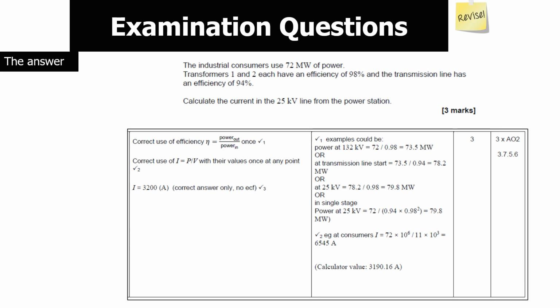The first point is at 132 kilovolts with an efficiency of 98%, so we do 72 over 0.98, giving 73.5 megawatts at that point. The next section has an efficiency of 94%, so we divide by 0.94, giving 78.2 megawatts at the start of transmission. Then you work it all through, pop in your values, and at the end do I equals P over V to get the answer of 3,190 amps.